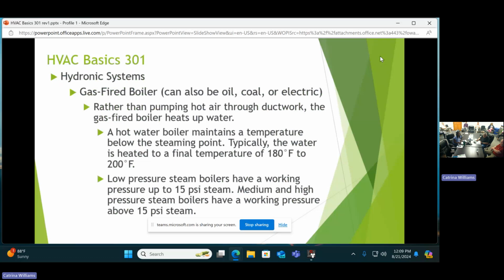Now, what if you wanted to make that 32 degree water into ice? To go from water to ice, we're changing state now, the latent heat we've been talking about. It takes 144 BTU to go from water to ice because we're changing state. So almost as many BTU there as the difference between steam and ice.